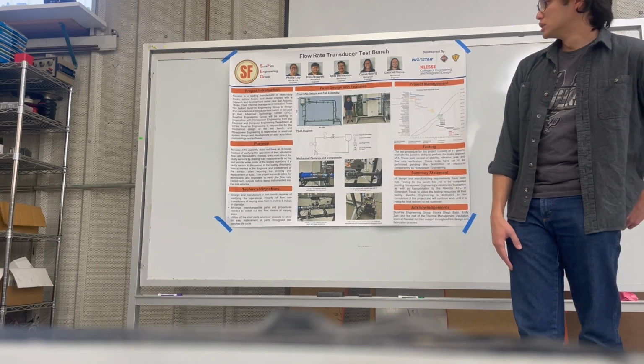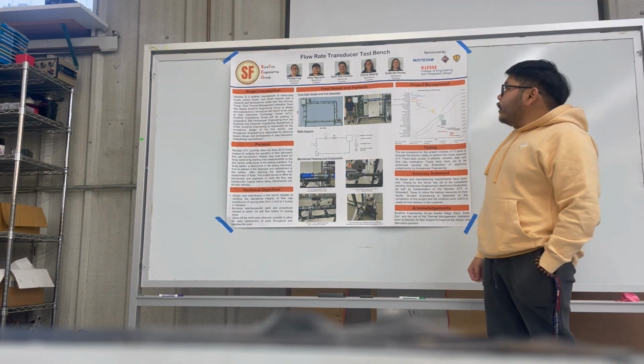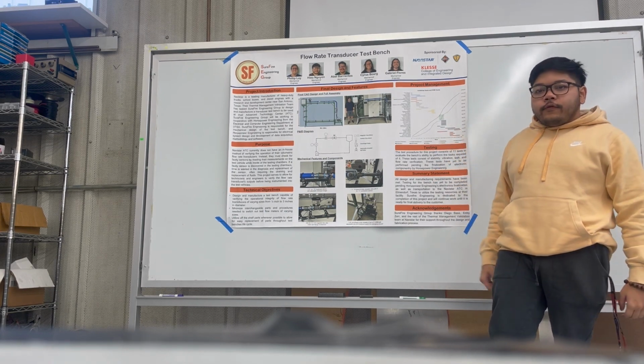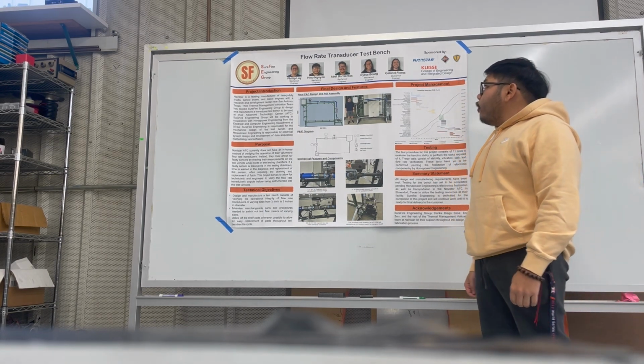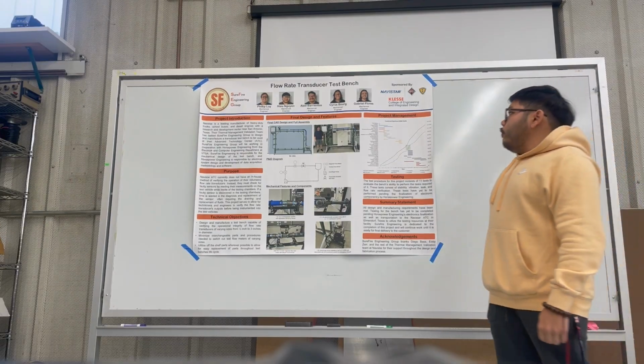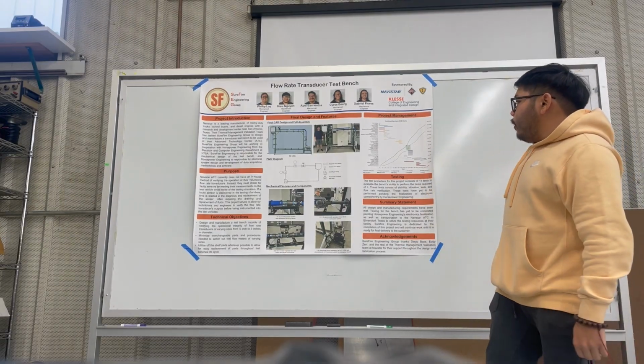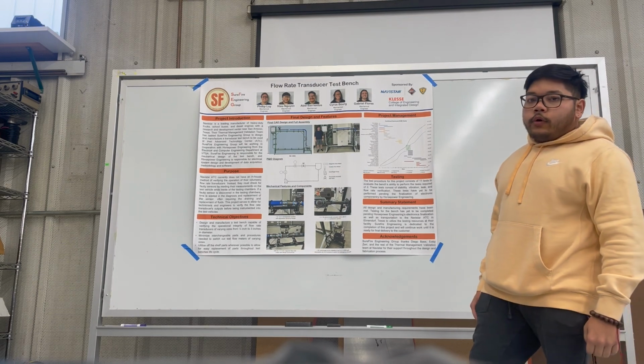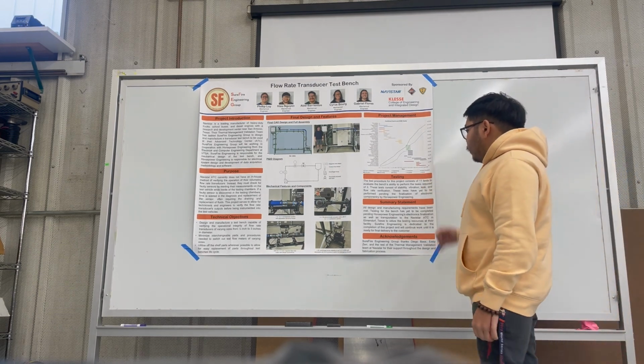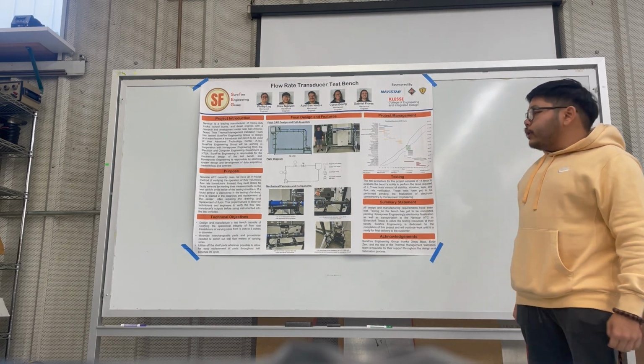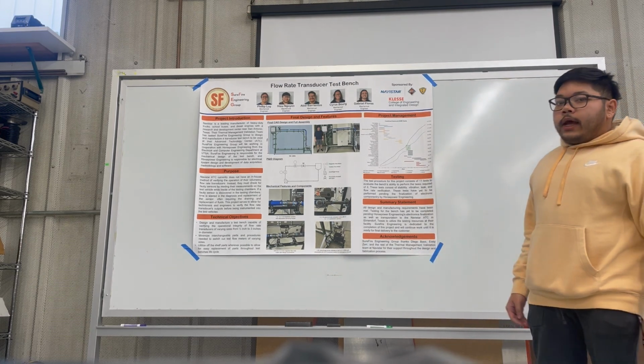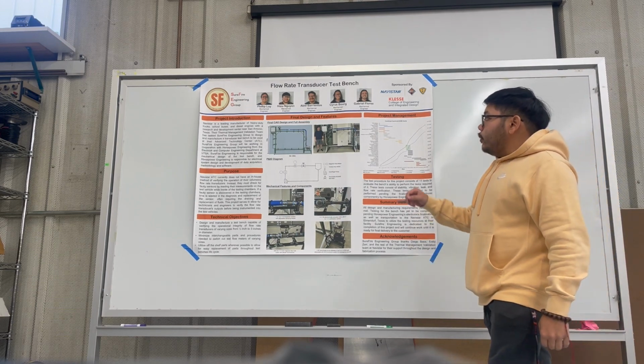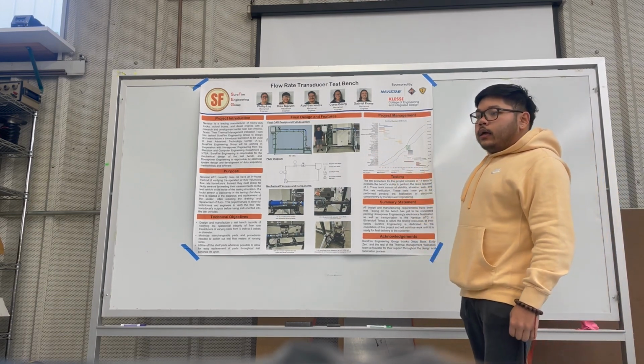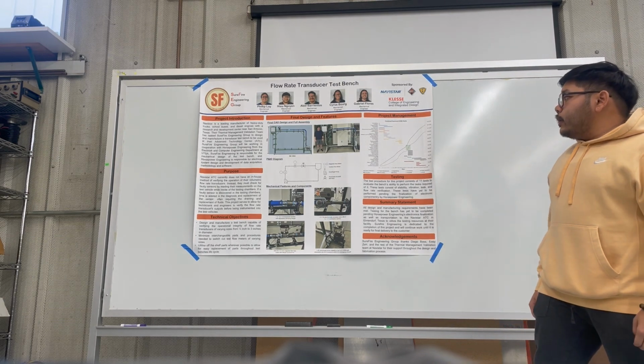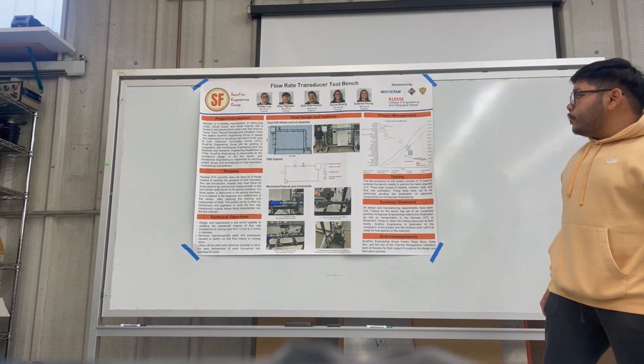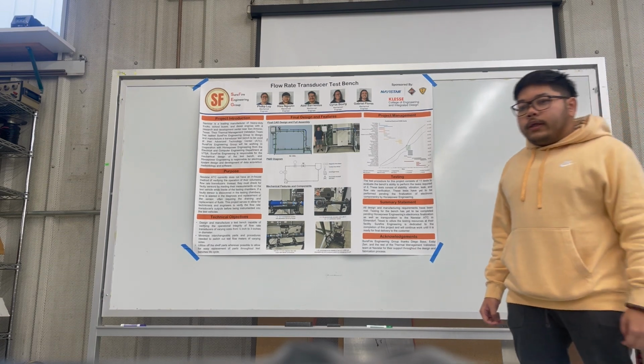My name is Hugh, and I was the quality engineer for this project, for the flow rate transducer test bench. Okay, so for the flow rate transducer test bench, we're going to perform 11 tests total. These tests consist of stability, vibration, leakage, and the actual verification between the master flow sensor and the test sensor, which our master flow sensor was a magnetic flow sensor and the other one was a turbine sensor.